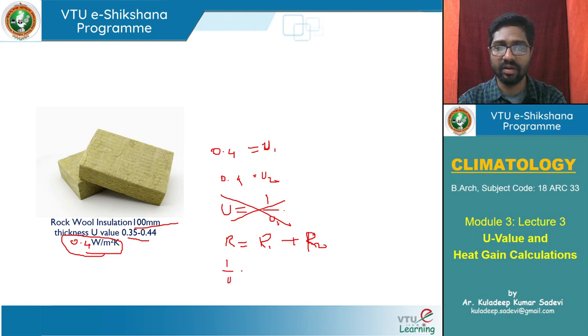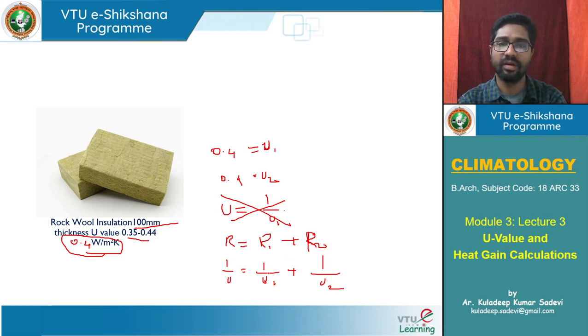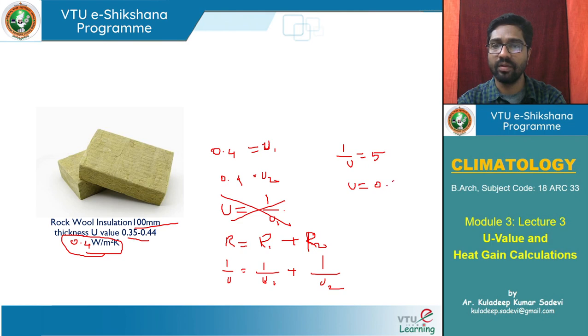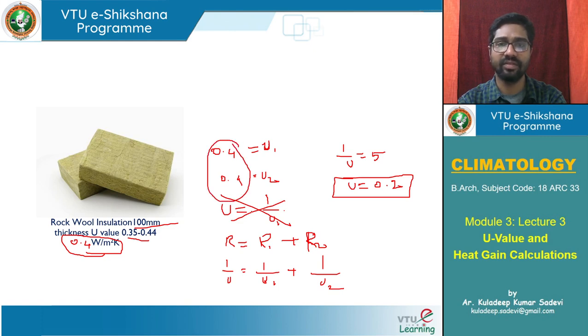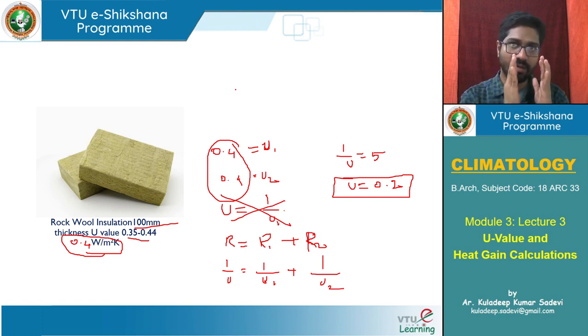When adding two layers together where 1/U = 1/U1 + 1/U2: with U1 and U2 both equal to 0.4, we get 1/0.4 = 2.5 for each, so 1/U = 2.5 + 2.5 = 5, therefore U = 1/5 = 0.2 W/m²·K. This shows we must not directly add U1 + U2 (which would give 0.8), because adding more material increases resistance, which decreases U-value, giving the correct answer of 0.2.